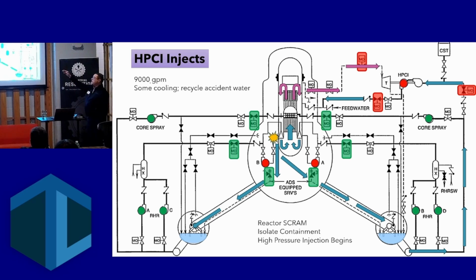And Tim, just like I had said earlier, high pressure coolant injection begins, and that's at 9,000 GPM. So right now, it's actually going to be a steam-driven pump. This motor-operated valve, and this motor-operated valve, and this motor-operated valve all reposition because they're open on de-energization. And then that puts the steam to the turbine drive on that HPCI pump, and then we're pushing a whole lot of water into the core right now. In fact, it's going to go on the outside, push its way down the downcomer, and then maintain coolant level here. But I can't do this forever because this is not a cooling method.